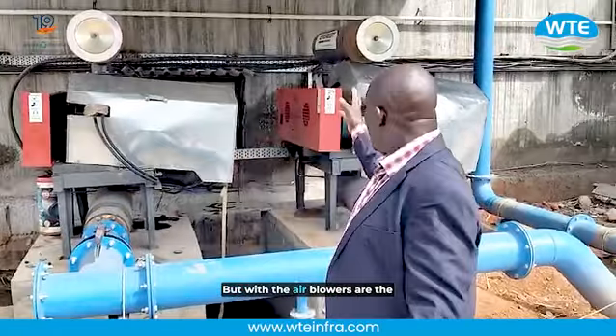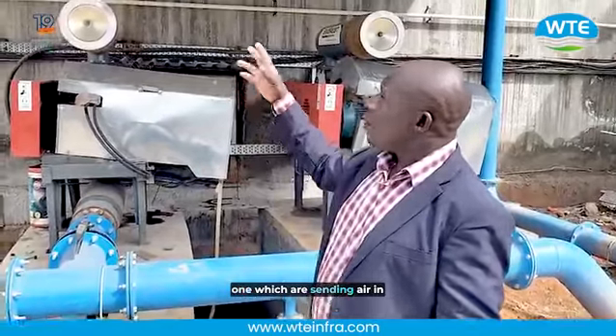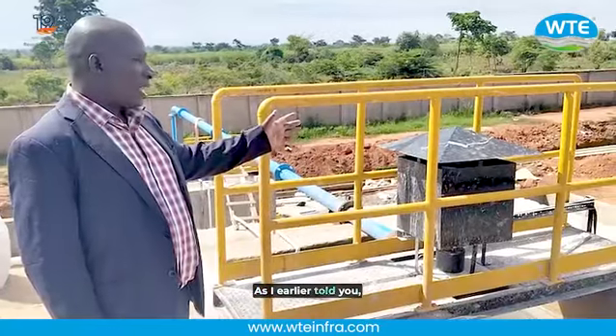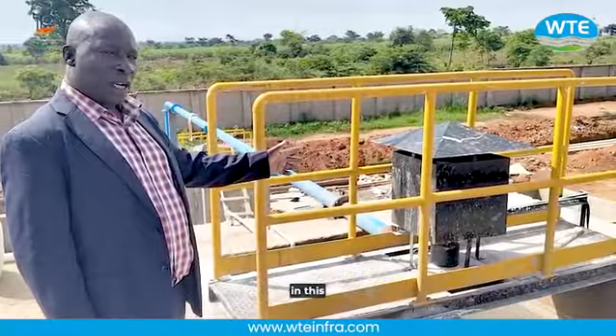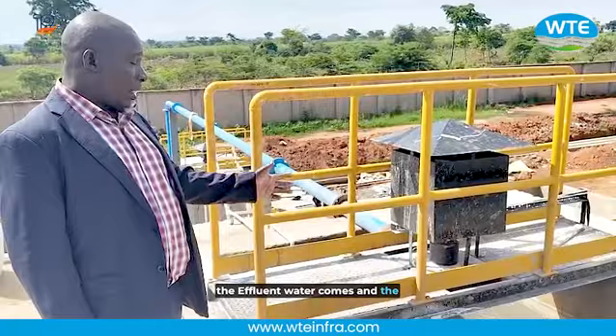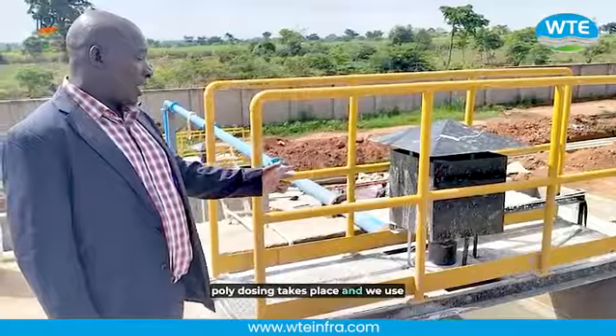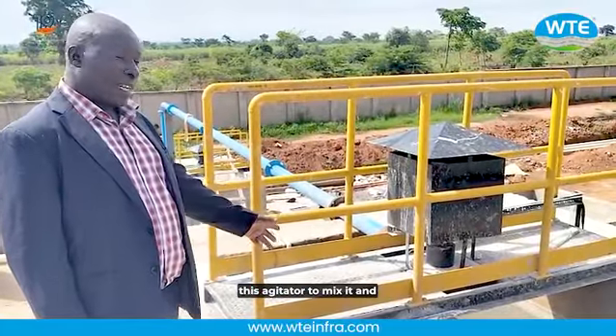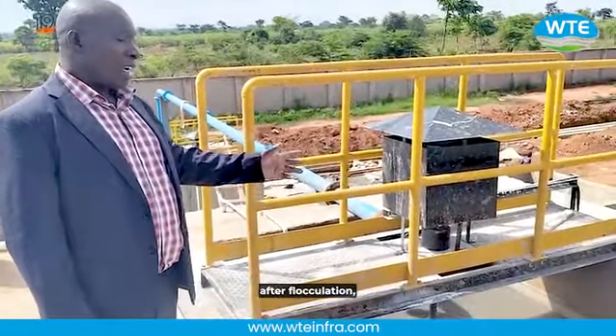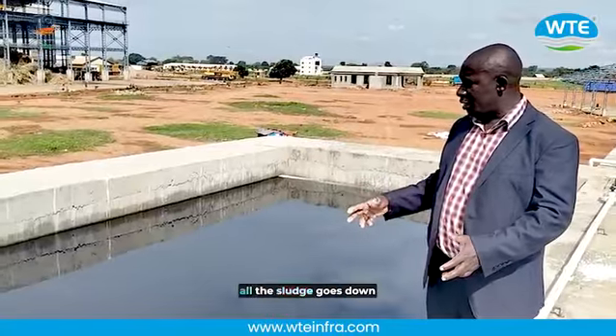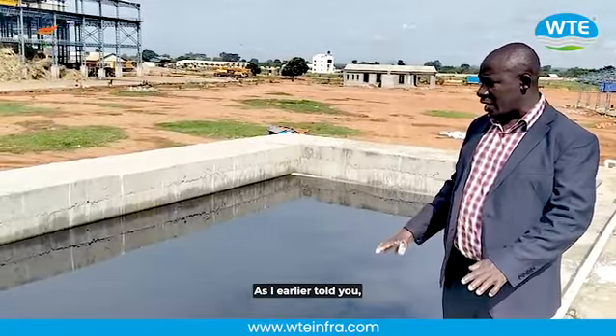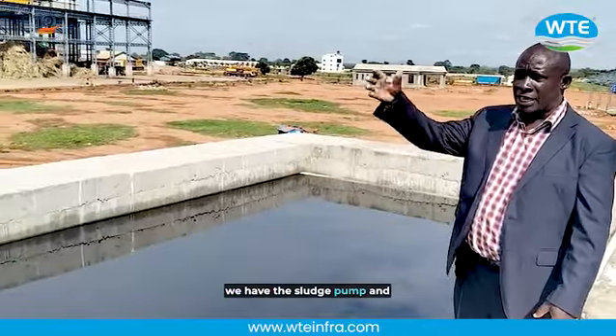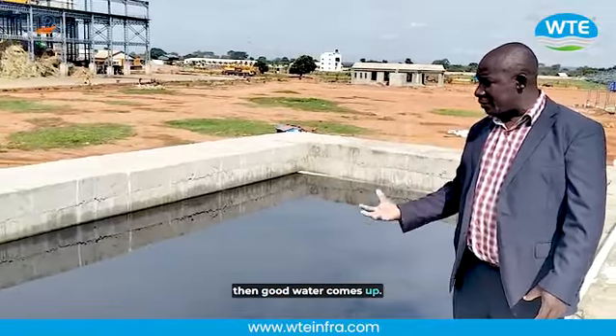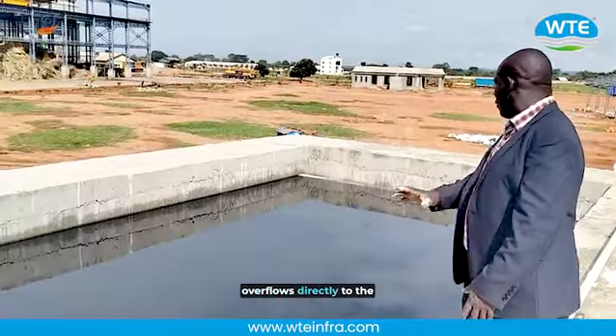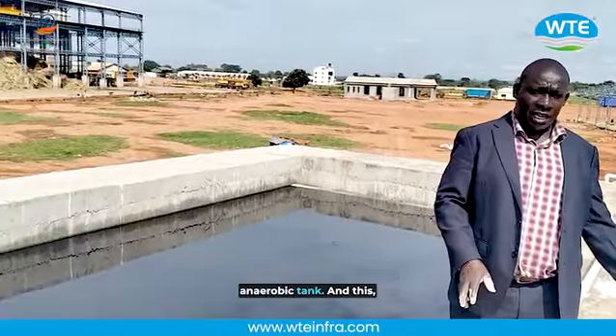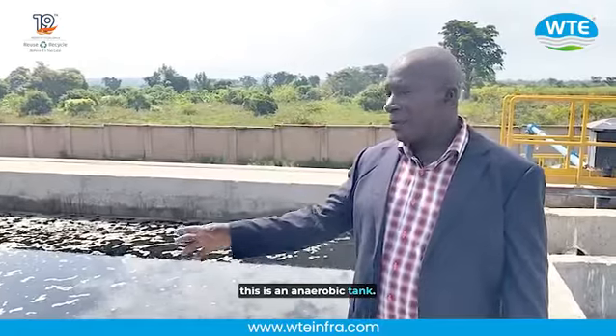These air blowers are the ones which are putting air in this tank. The effluent water comes and the poly dosing takes place, and we use this agitator to mix it, and after flocculation, all the sludge goes down and settles down. As I've earlier told you, we have the sludge pump, and then good water comes up. This water continues and overflows directly to the anaerobic tank. This is an anaerobic tank.